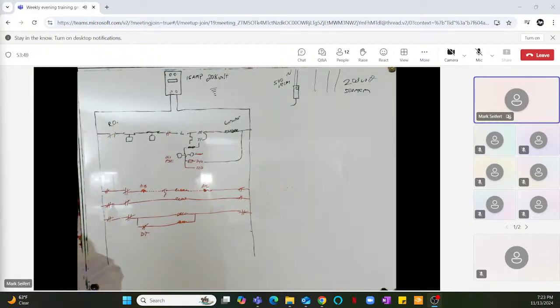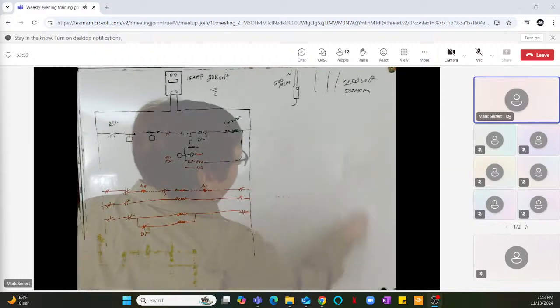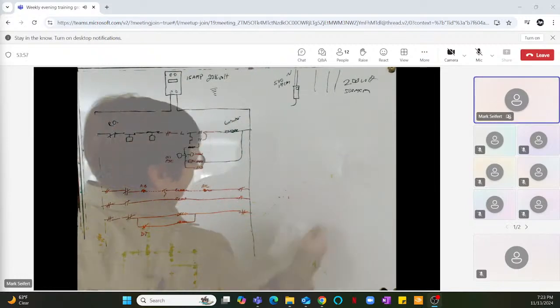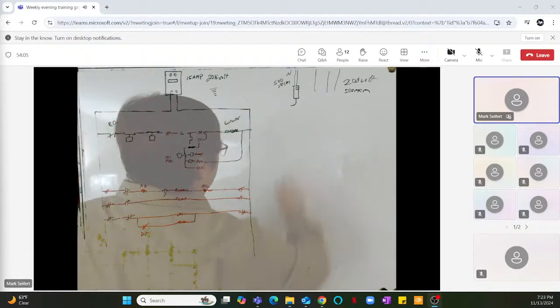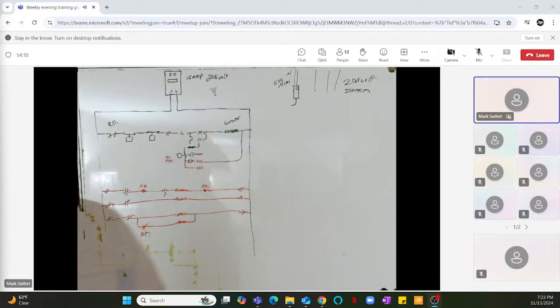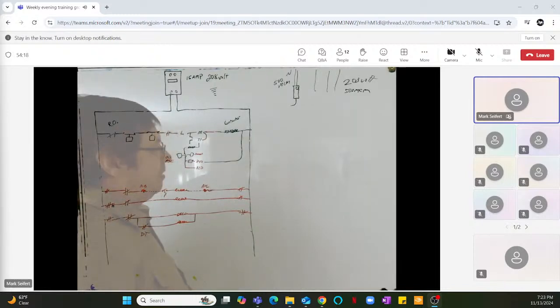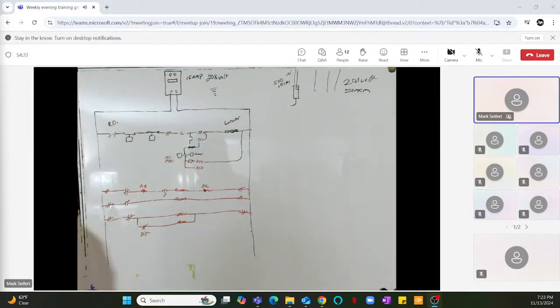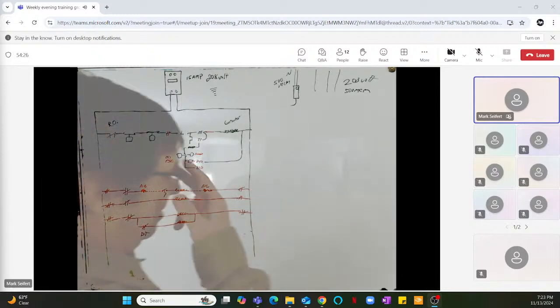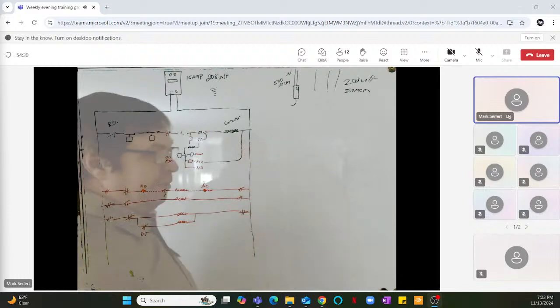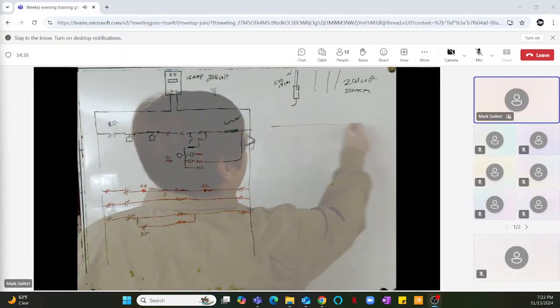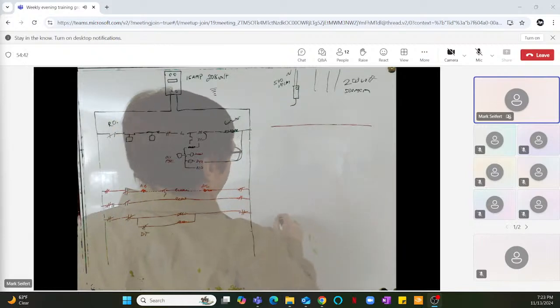You guys know that in some of our stores, especially the older ones that were made right, and they're starting to do it now on newer ones, we have under case returns, right? And in the winter time it's not nearly as important as it is in summertime, but it's crucial that we know how those things work in the winter time, and to look for them and identify any problems, maybe a damper needs to be moved to get more air out through the under case returns. But first of all, make sure that your store furnaces are working. Now's the time.